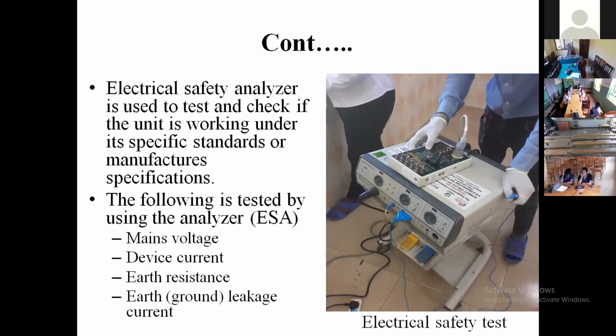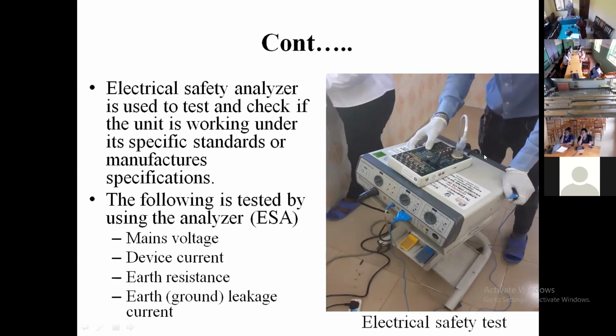So we check for device current, we check for earth resistance, and we check for earth ground leakage current during our electrical safety analyzing. As you can see, this is the picture.